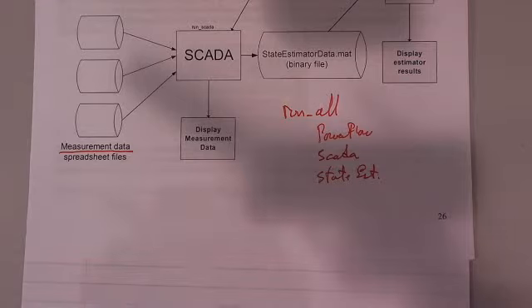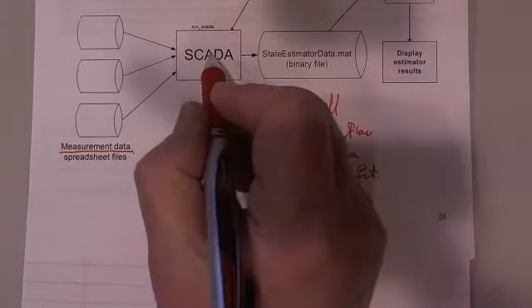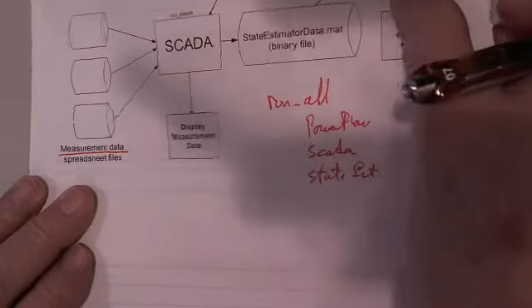I've got an injection measurement on each of the buses, and so forth and so on, all the possible measurements. And the idea is that the SCADA system says, I'll just draw this over here. It says, let's see, we're at 5 here. Suppose I've got a flow out here from bus 1 to 2. I don't know what the actual is, but let's say it's reading 12.6 megawatts. Okay, this is the actual.